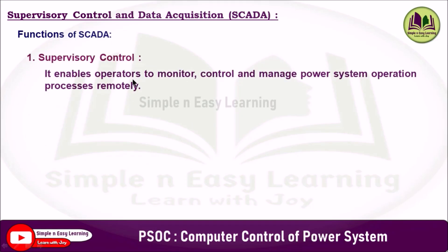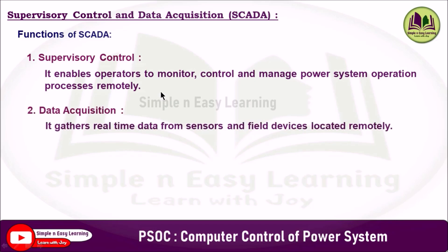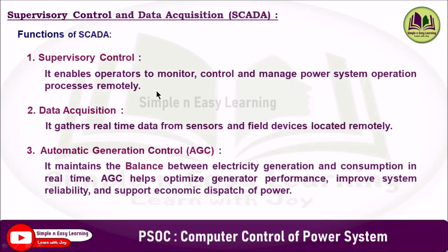The first function is supervisory control, which enables operators to monitor, control and manage power system operation processes remotely. The second is data acquisition, which gathers real-time data from sensors and field devices located remotely. The third is automatic generation control (AGC), which is responsible for maintaining the balance between electricity generation and consumption in real-time. It automatically adjusts the output of multiple generators to ensure stable system frequency and proper power flow, optimizing generator performance and supporting economic dispatch.